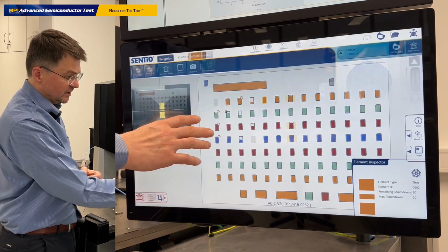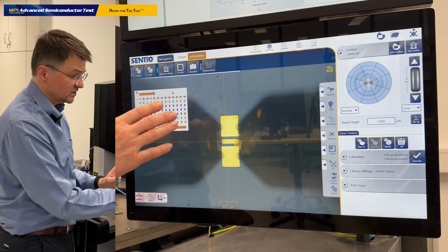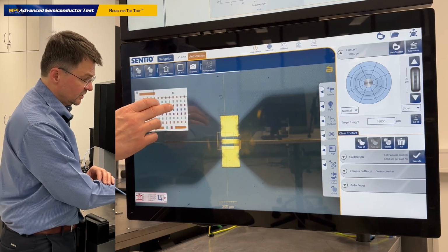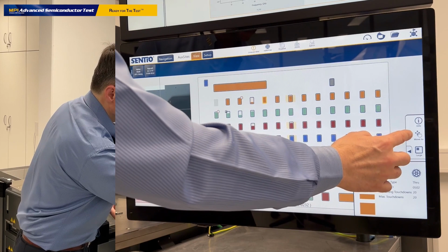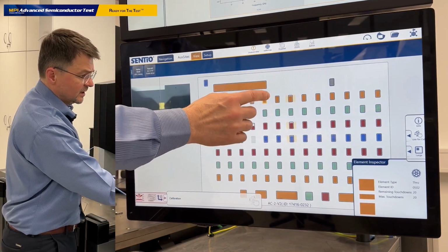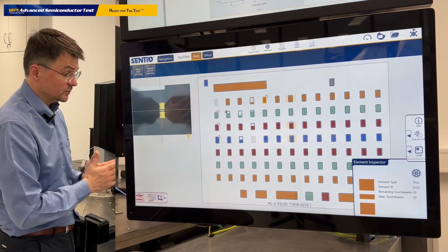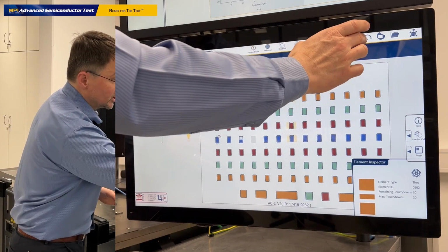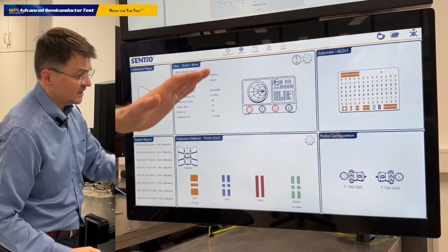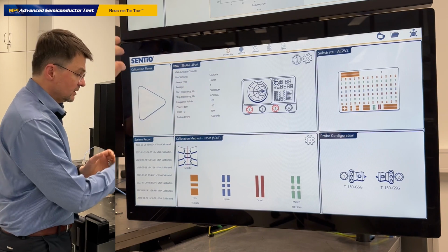We've just moved to the neighbor element, and what we see is brilliant: it's a never touched, never used element, so we really like to use it for the calibration process. I select the tool used for the cal, I select the standard, and it's marked that this element will be used for the calibration process. And now I can simply go back to my settings of Calibria and continue to set up my calibration workflow.